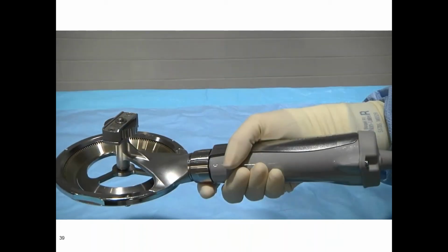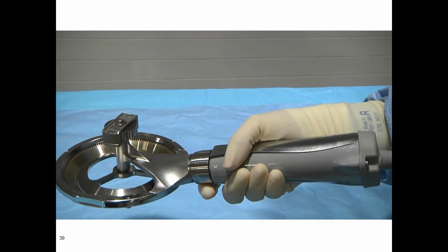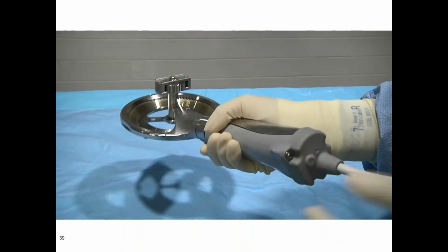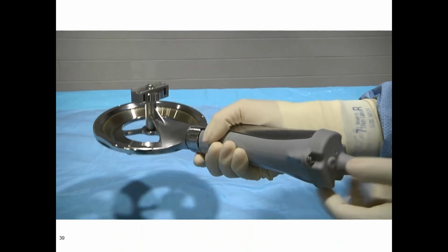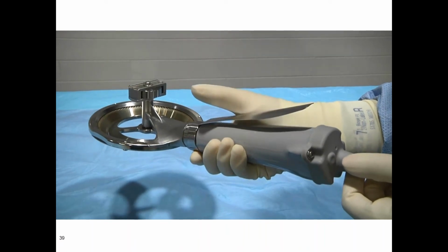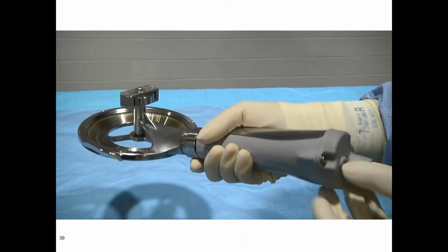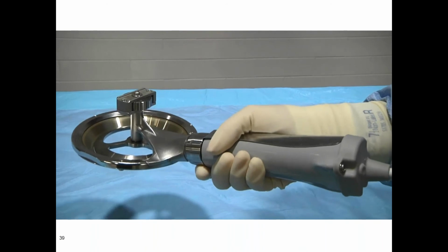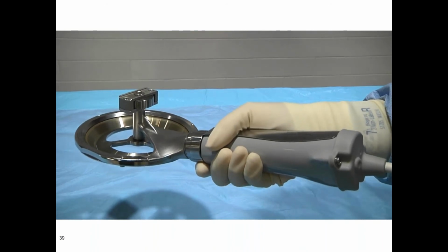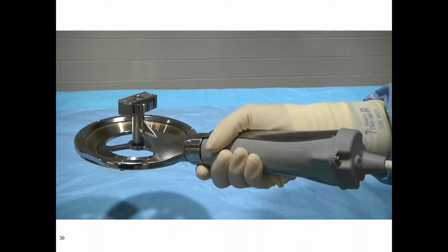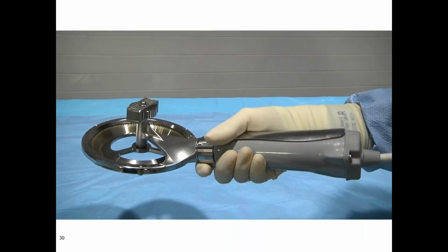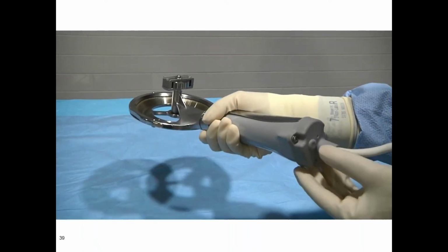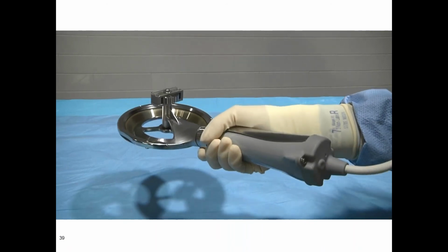Note, if the instrument is not activated within 4 to 7 seconds, the lever must be released and re-engaged to reset the ready timer. This is for safety purposes and does not allow the device to accidentally be activated if placed lever side down. Releasing the lever will deactivate the device.